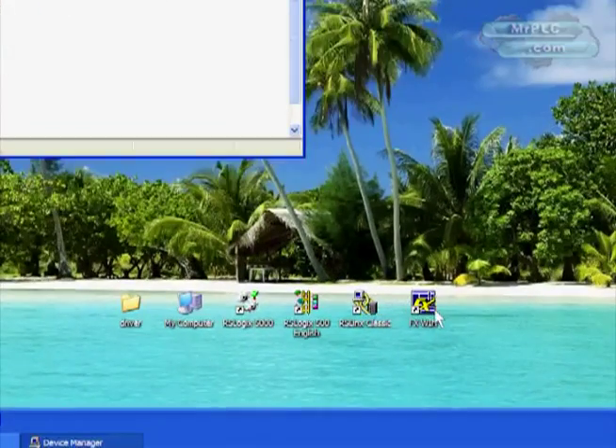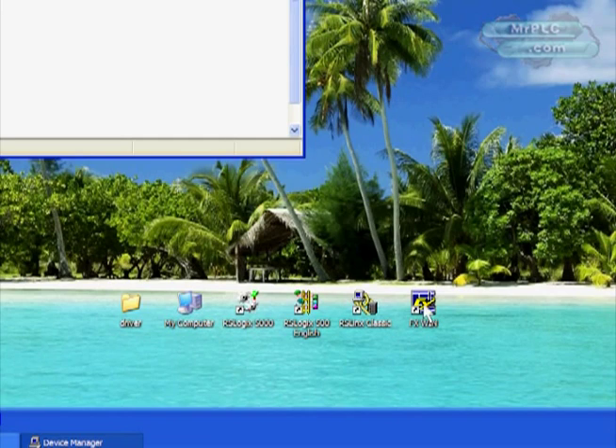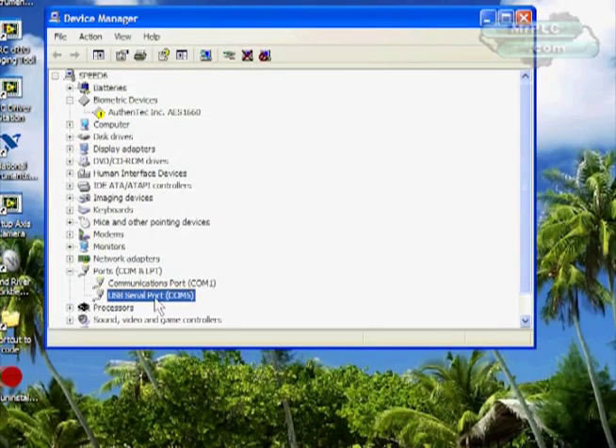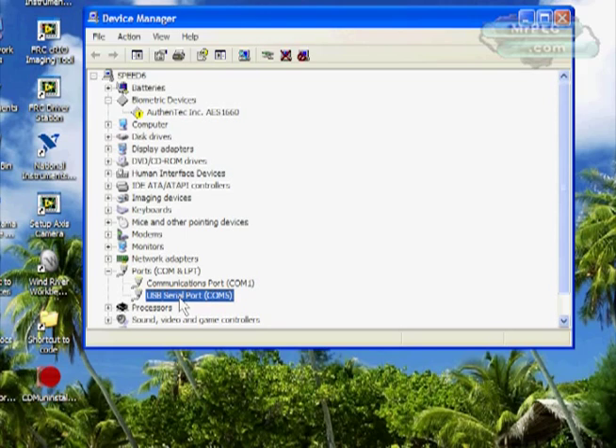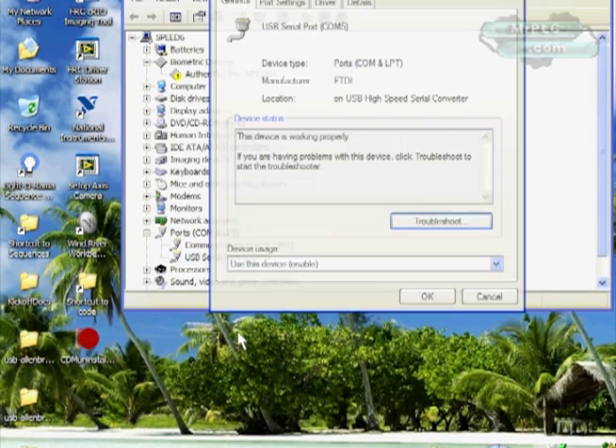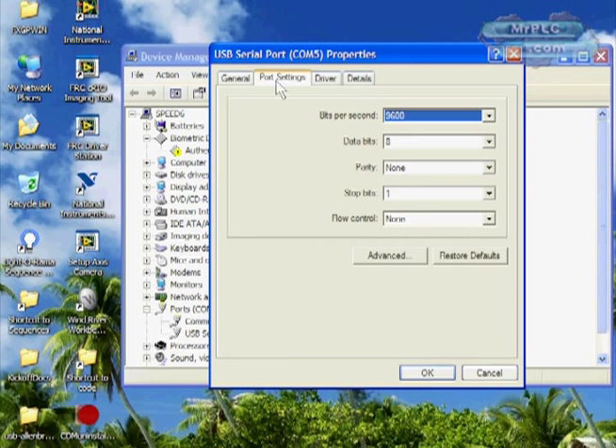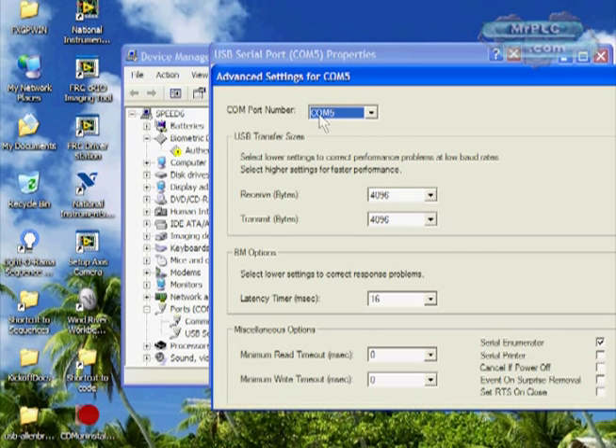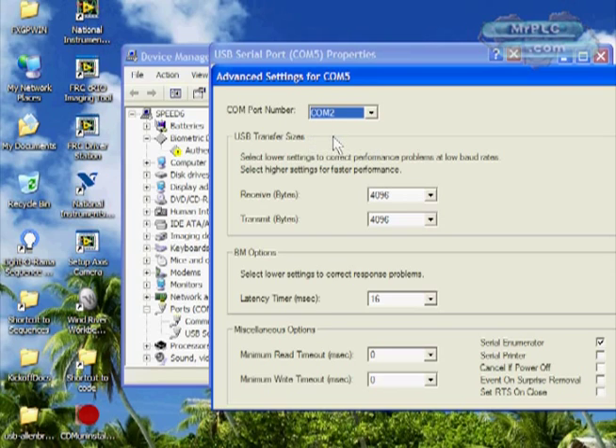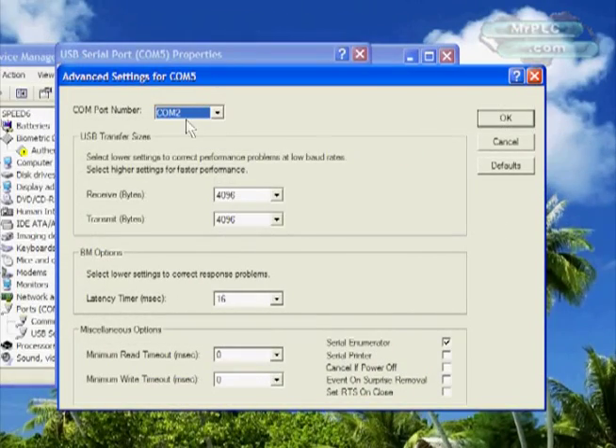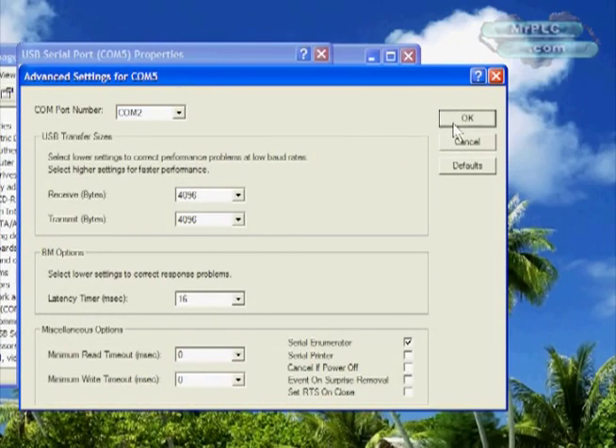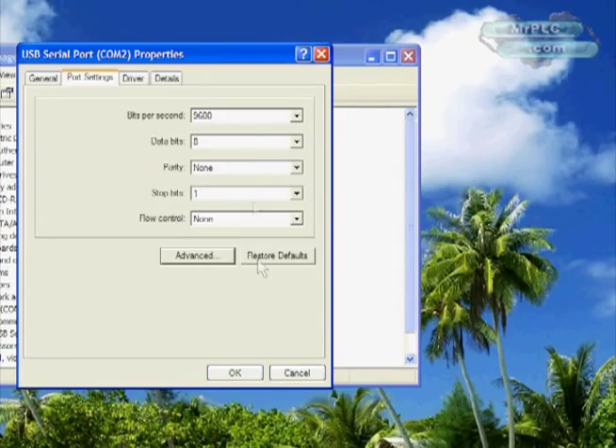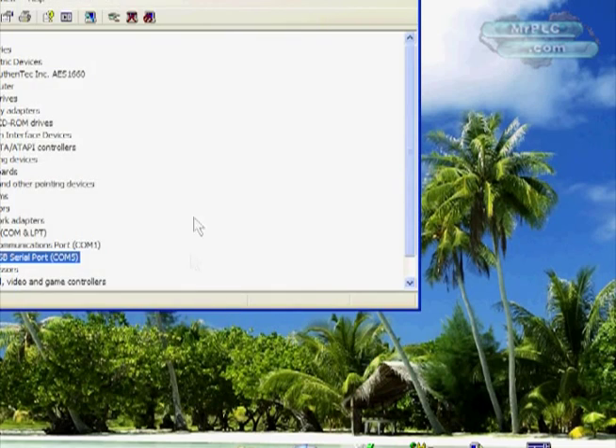How to fix that is we right click on our USB serial port and click on properties. Then go to port settings and advanced. Right here is our COM port assignment for the USB. We're going to remap that to COM2. COM2 is a choice that's available in FXWin. We're going to tell the cable to map to that virtual port instead.